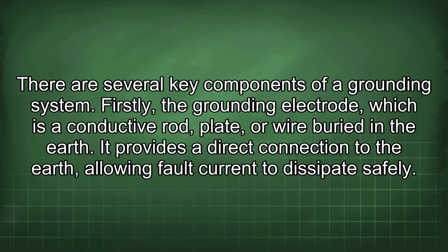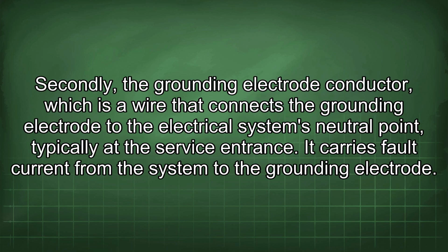There are several key components of a grounding system. Firstly, the grounding electrode, which is a conductive rod, plate, or wire buried in the earth. It provides a direct connection to the earth, allowing fault current to dissipate safely. Secondly, the grounding electrode conductor, which is a wire that connects the grounding electrode to the electrical system's neutral point, typically at the service entrance. It carries fault current from the system to the grounding electrode.